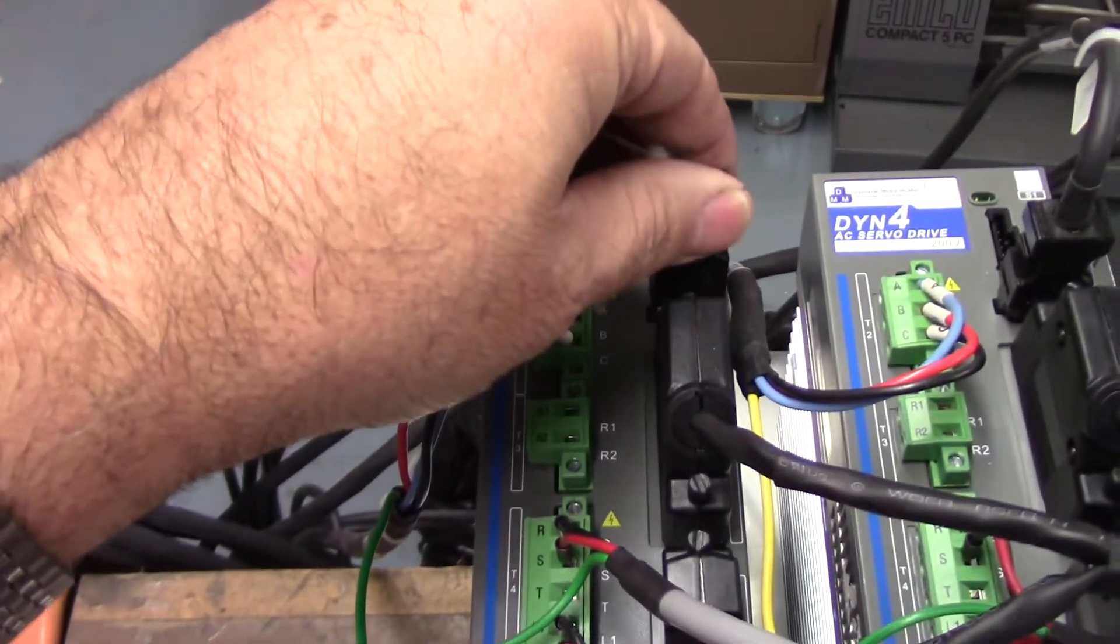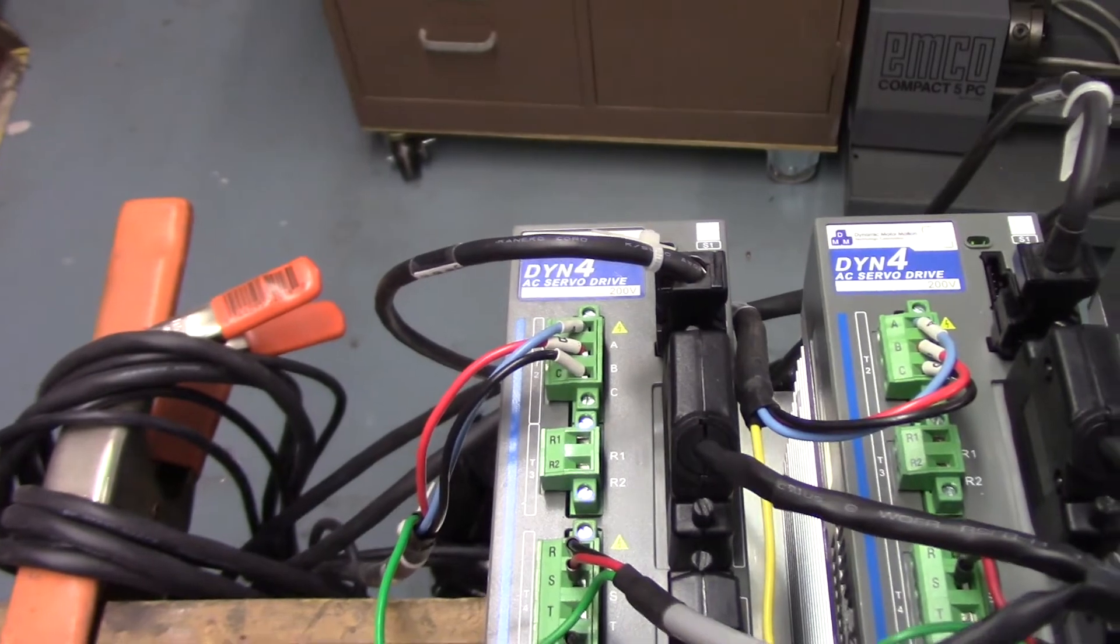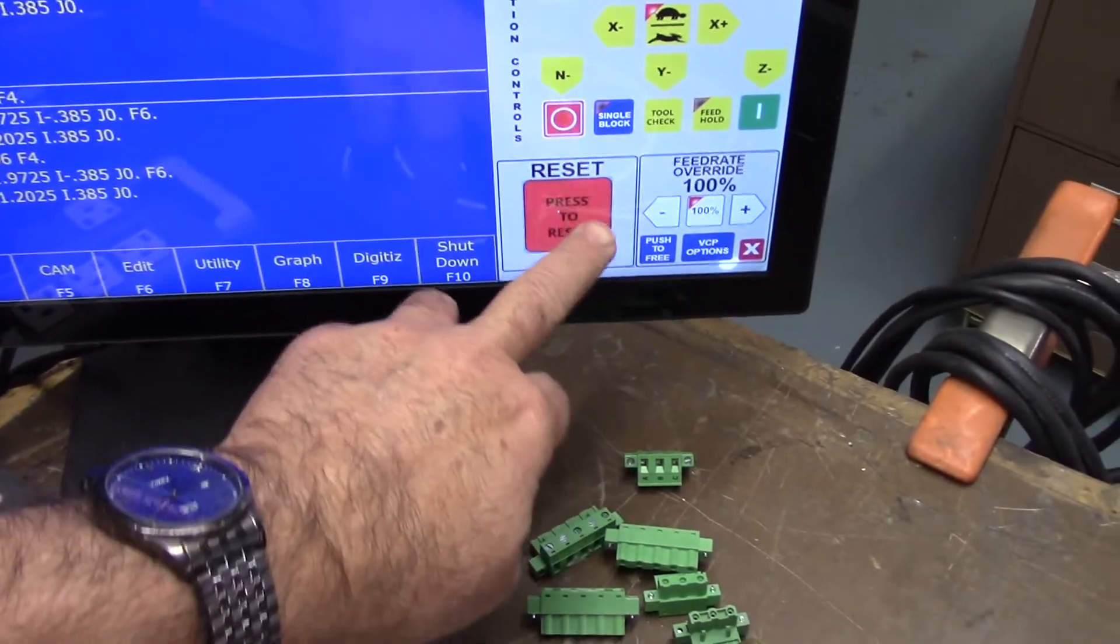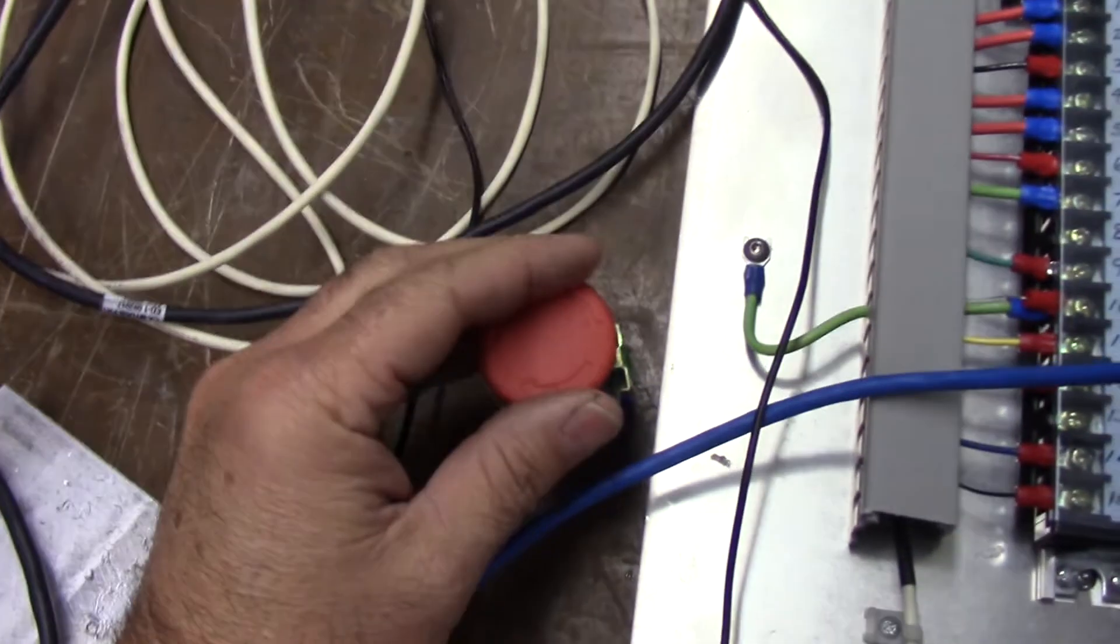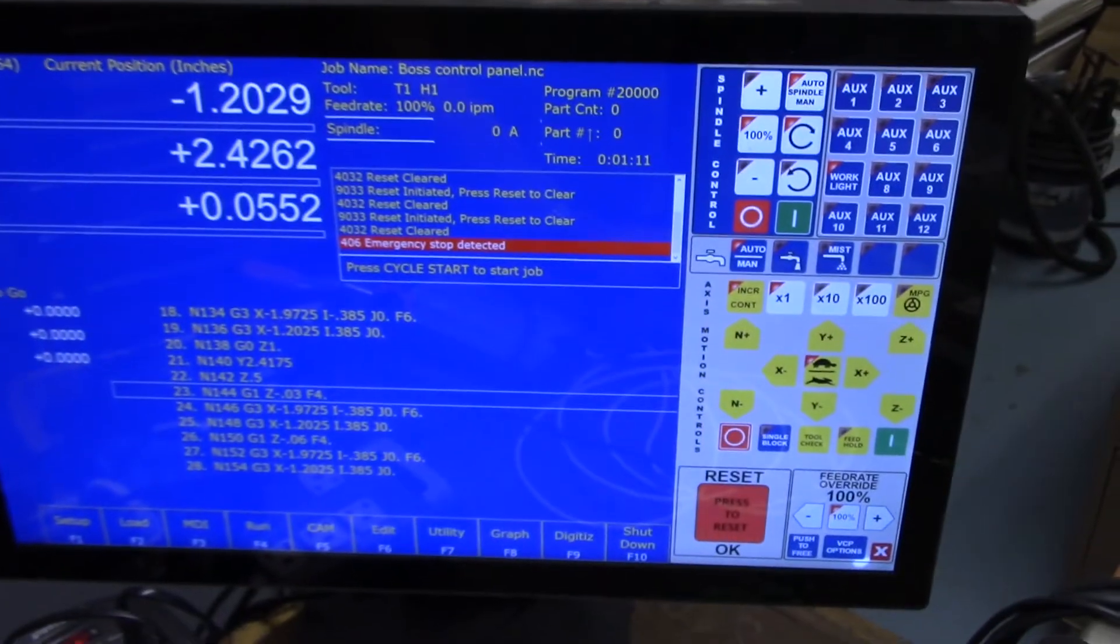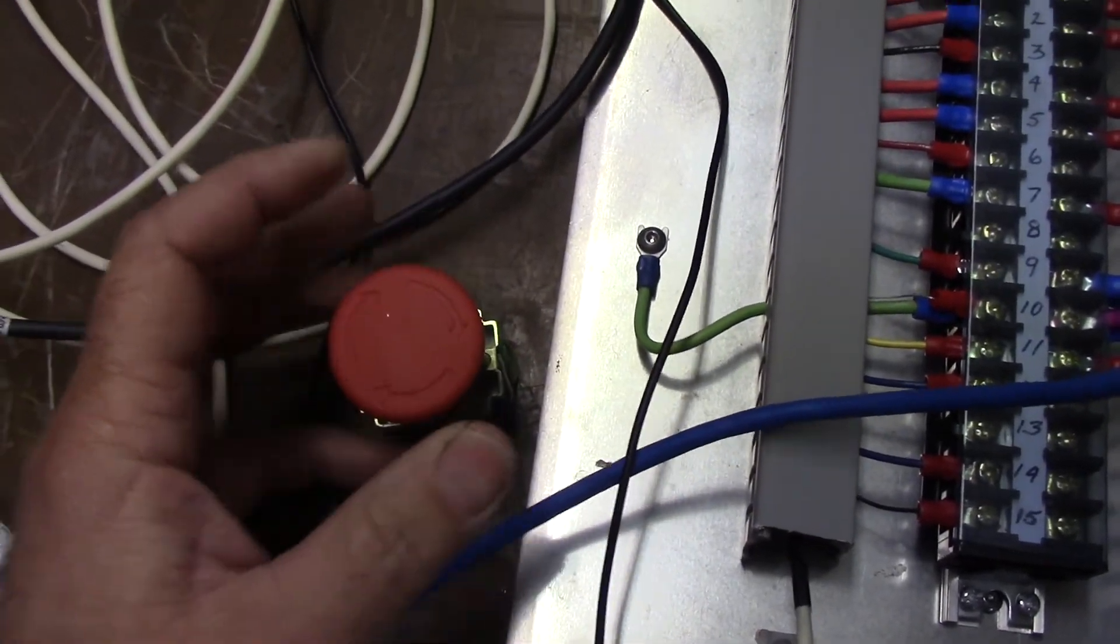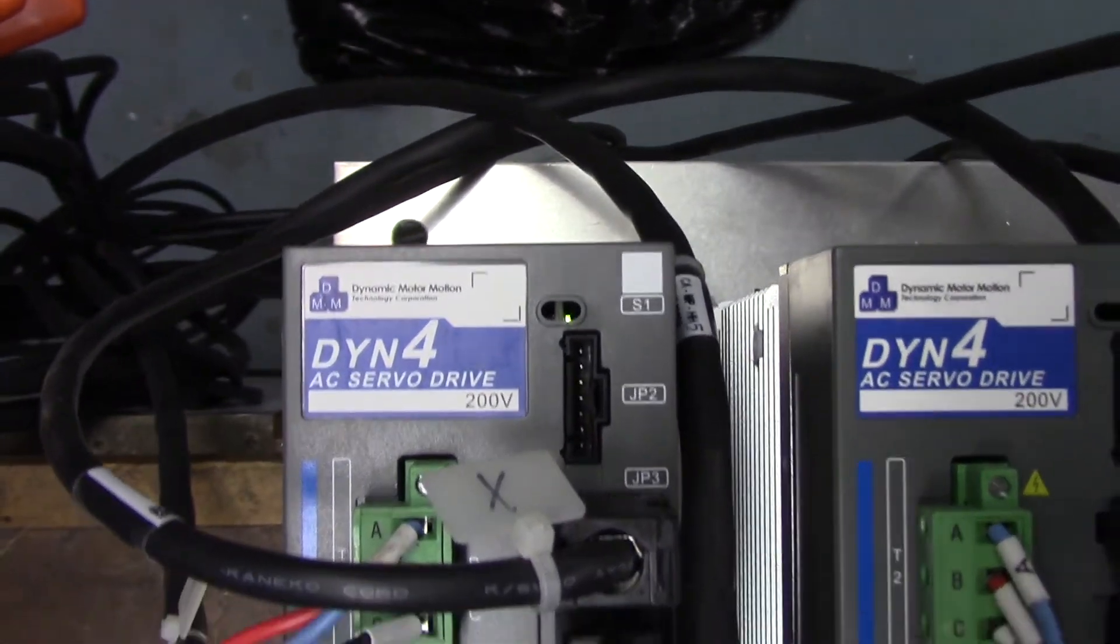Now what I'm going to do is reconnect the encoder cable. You cannot reset that drive by pressing the virtual control panel reset button - you have to press the E-stop button to cycle through a fault. I'm pressing it. Emergency stop detected. I'm going to release it and you'll hear the E-stop relay close. It is closed. You'll notice down here that the drive is reset.